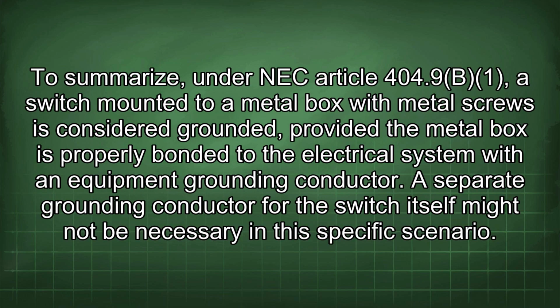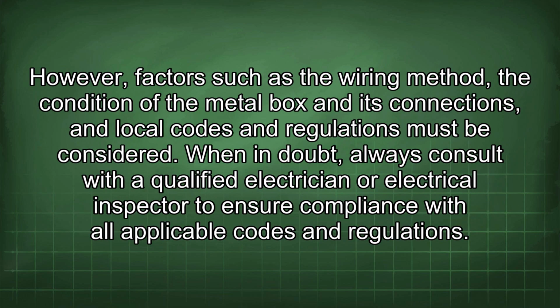To summarize, under NEC Article 404.9(B), a switch mounted to a metal box with metal screws is considered grounded, provided the metal box is properly bonded to the electrical system with an equipment grounding conductor. A separate grounding conductor for the switch itself might not be necessary in this specific scenario. However, factors such as the wiring method, the condition of the metal box and its connections, and local codes and regulations must be considered. When in doubt, always consult with a qualified electrician or electrical inspector to ensure compliance with all applicable codes and regulations.